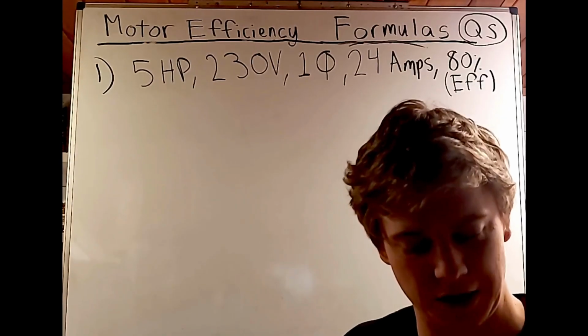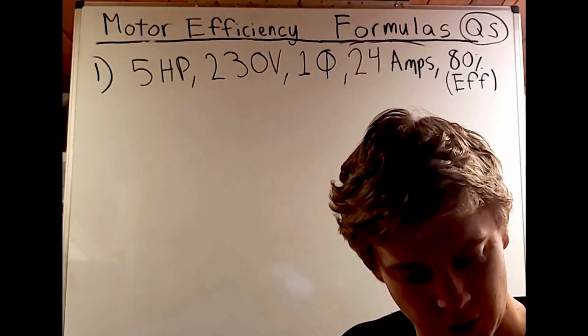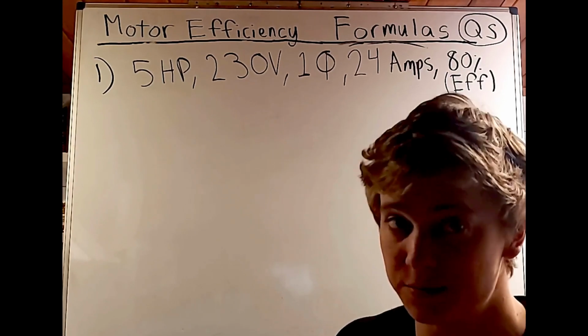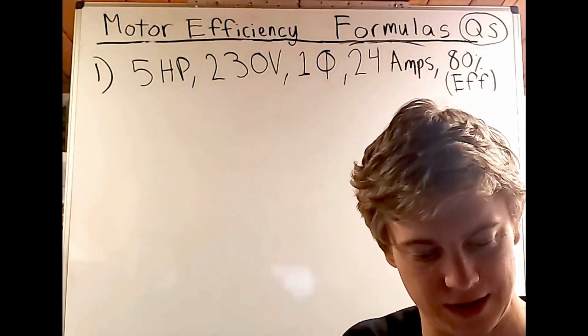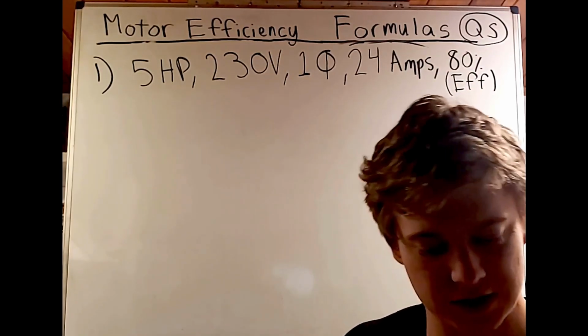Okay, so if you didn't know how to read that table, they tell you directions. There's the horsepower on the left side, and then you have your volts above that, and all those numbers that you see are your amps. So read the top of it: full load current in amperes, single phase alternating current.